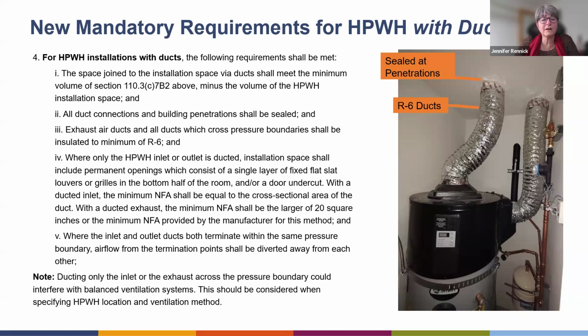What the code kind of gets at, if you take a look at the note at the bottom—this is part of the code language excerpted—it does say to really think about it. For example, if you're ducting only the inlet or the exhaust across the pressure boundary, you could interfere with balanced ventilation systems. This should be considered when specifying heat pump water heater location and ventilation method.